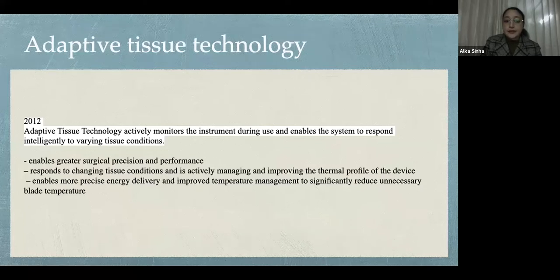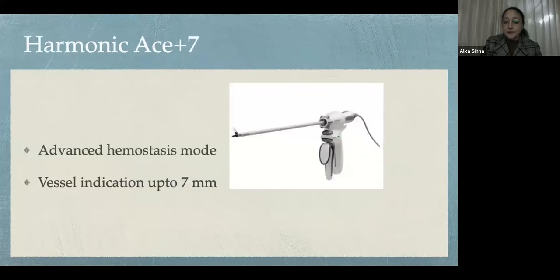As the tissue gets transected, the blades come into opposition and the temperature rises. This allows a feedback, and because of this, the temperature will not rise anymore. This enables more precise energy delivery and improves temperature management to significantly reduce the temperature at the tip. So this was the advantage in the Harmonic Ace Plus.